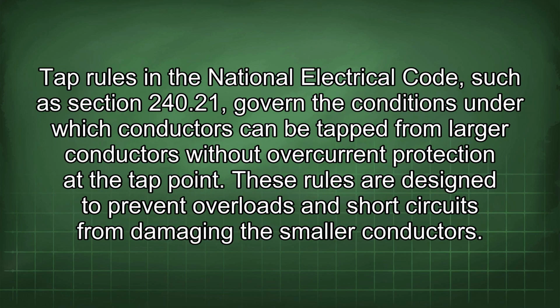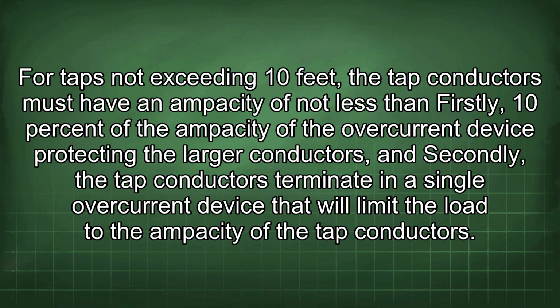Tap rules in the National Electrical Code, such as Section 240.21, govern the conditions under which conductors can be tapped from larger conductors without overcurrent protection at the tap point. These rules are designed to prevent overloads and short circuits from damaging the smaller conductors. For taps not exceeding 10 feet, the tap conductors must have an ampacity of not less than, firstly, 10% of the ampacity of the overcurrent device protecting the larger conductors, and secondly, the tap conductors terminate in a single overcurrent device that will limit the load to the ampacity of the tap conductors.